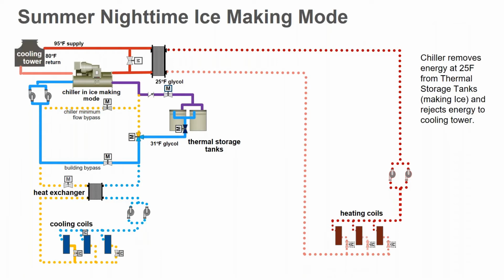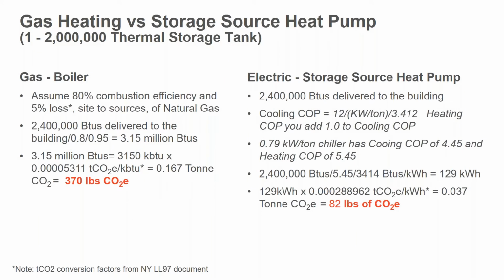So on that summer night, as I started describing, now you've got tanks that are water, mainly water, and you got to get rid of that energy out of this storage device. And so we're going to run those chillers at night. We're going to dump that energy out the cooling tower, get it out of the building, and now you have your thermal storage tanks devoid of energy, and they're all ice in the morning, ready to help the building cool in the next day. So let's take a look at some of the efficiencies.